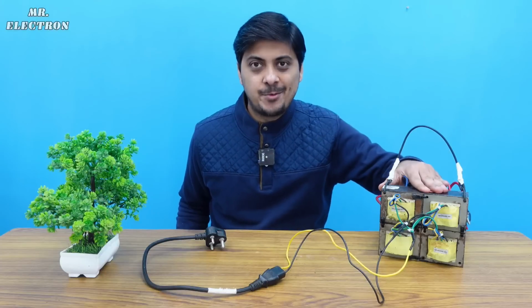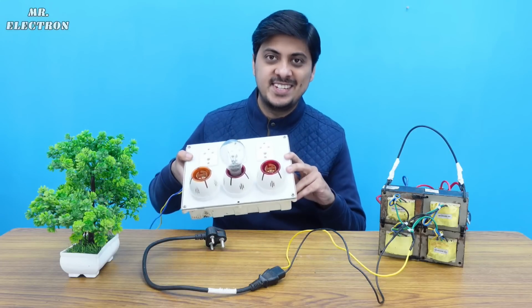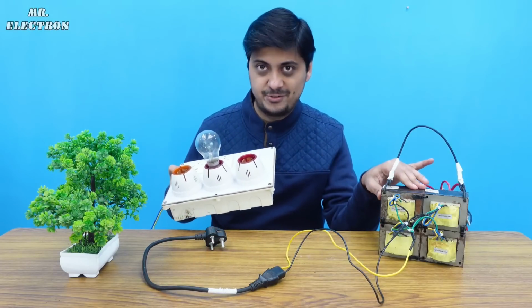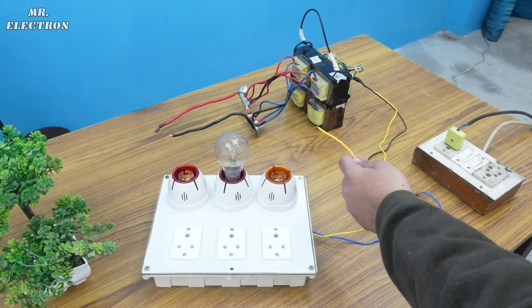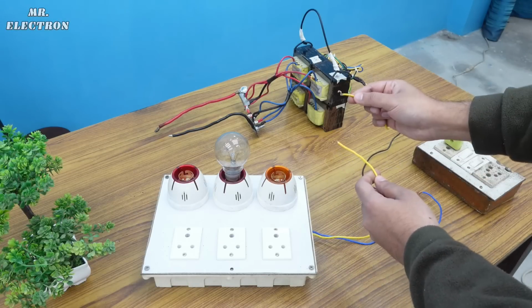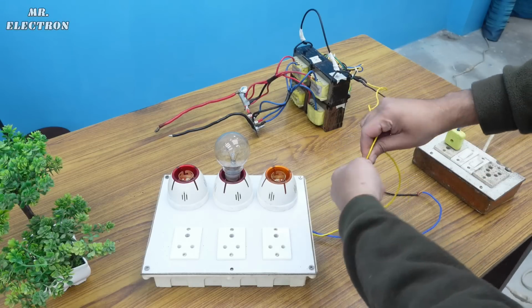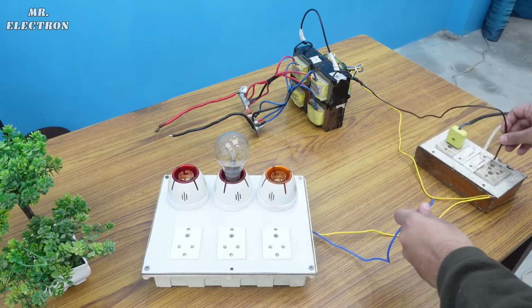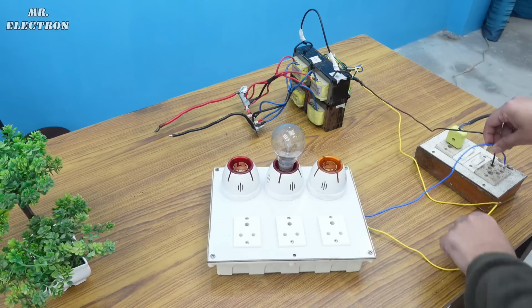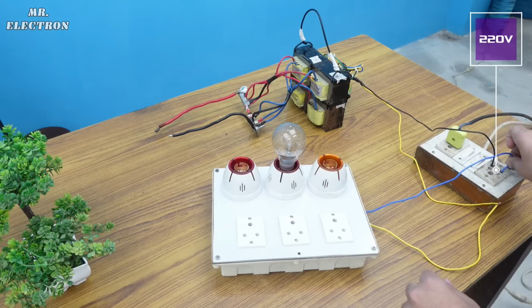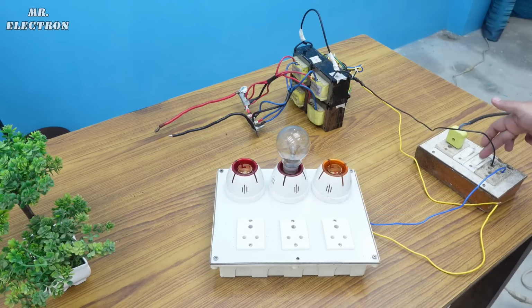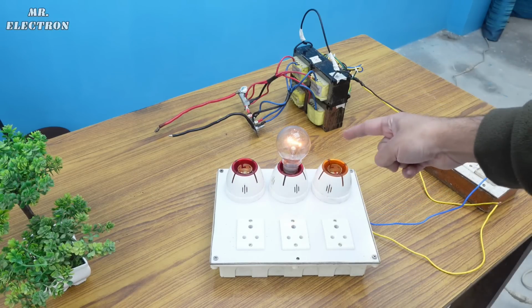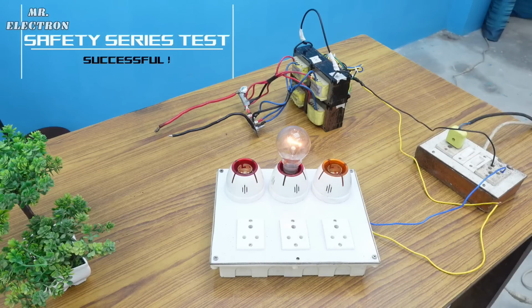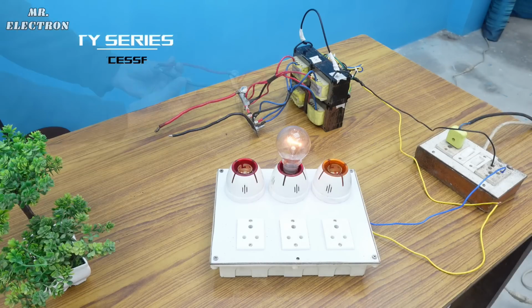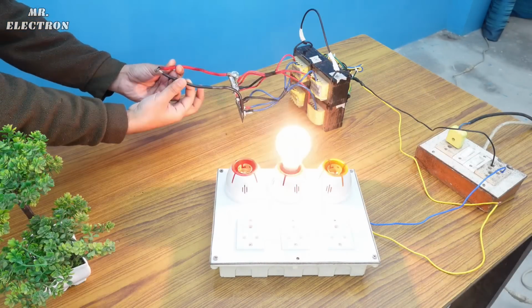It is finally complete. Now I'm going to use my series bulb to do the safety check first. Take one wire from the bulb and one from the transformer input and join them together. Now take the remaining two wires and connect them to your 220 volts home socket supply. Turning it on, the bulb is glowing dim, indicating that everything is fine. Anything else would indicate either improper connection or short circuit.